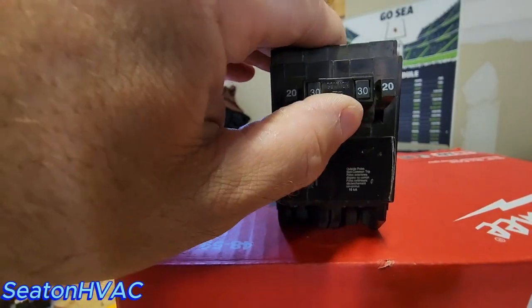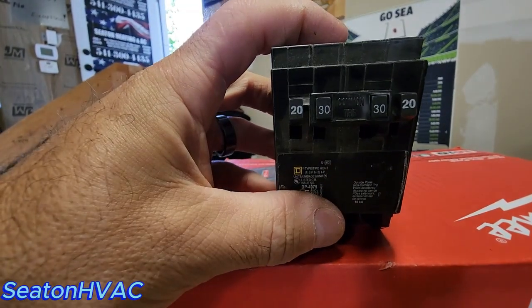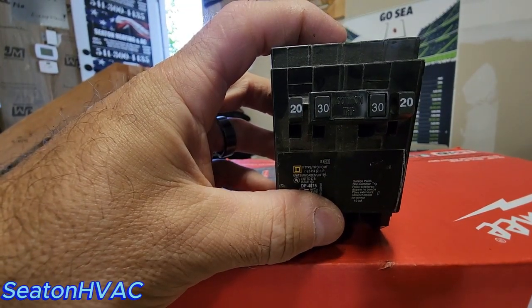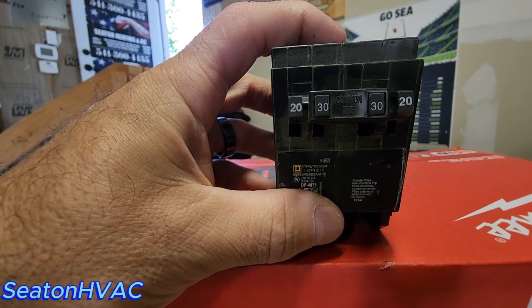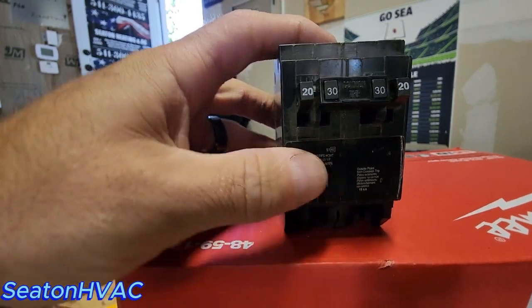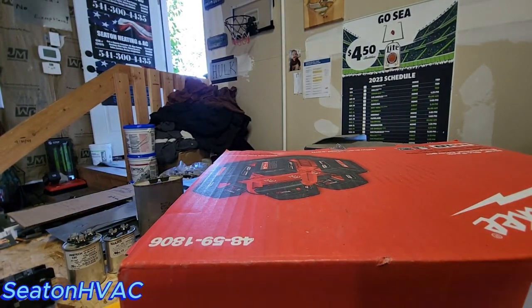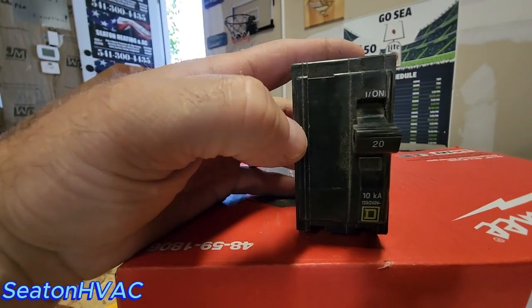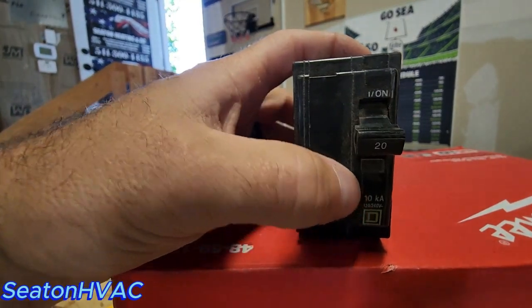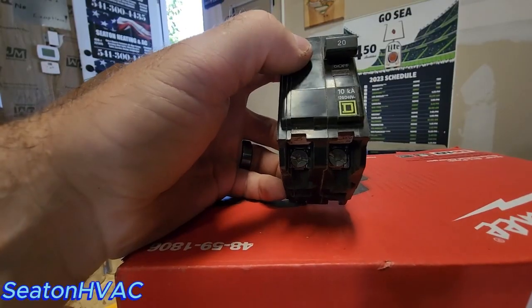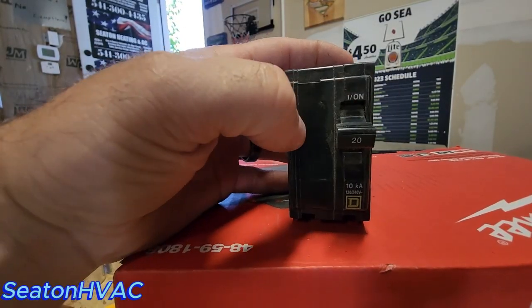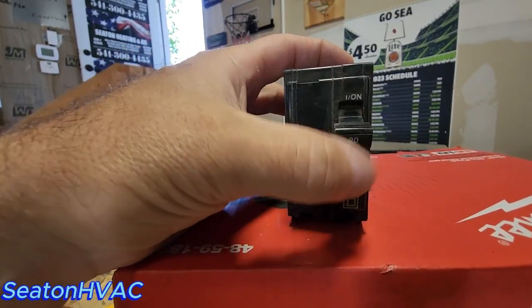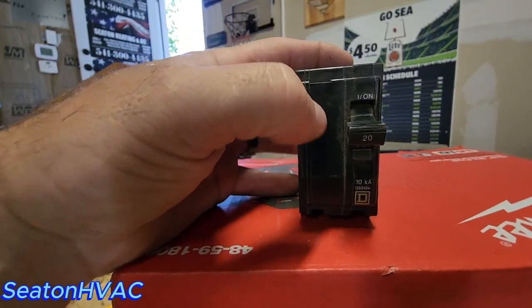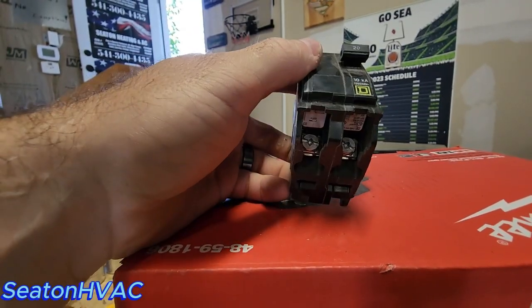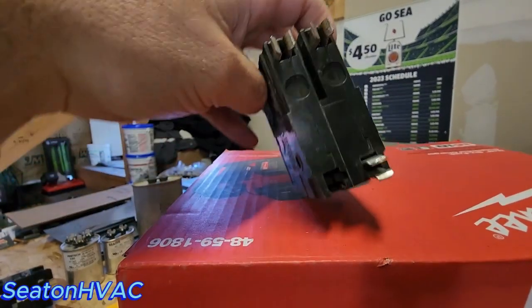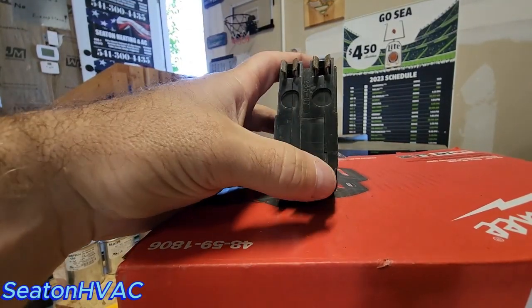And then this would be your more appliance that takes more power: range, dryer, HVAC equipment, you name it. So there's that one. All right, so here we got a standard Square D breaker, 20 amp. It's still a double pole. It just has the switch is different. It doesn't have two sides to it, it's just the way they make these ones. But it's still 240 volts, just like the other one. They mount different into the panel.